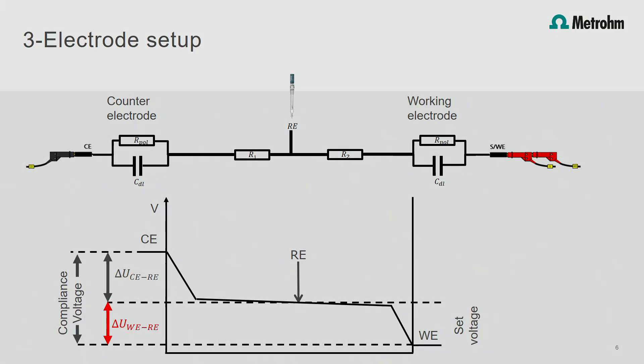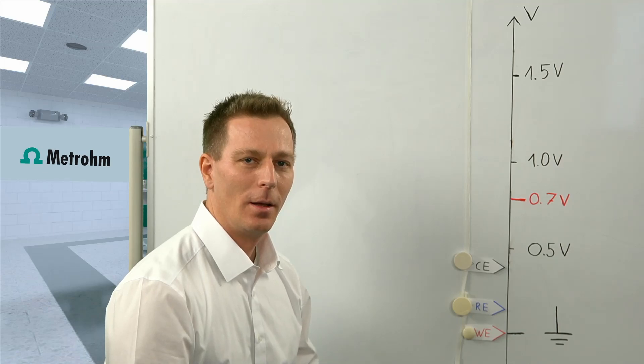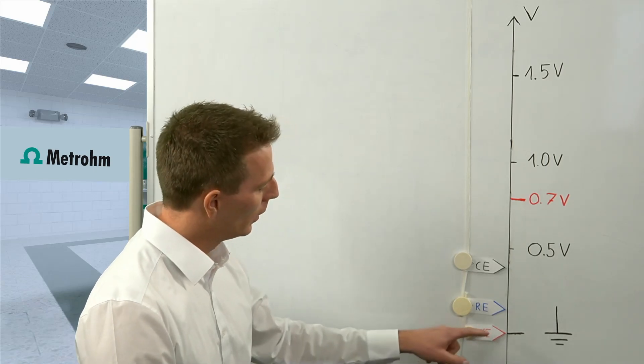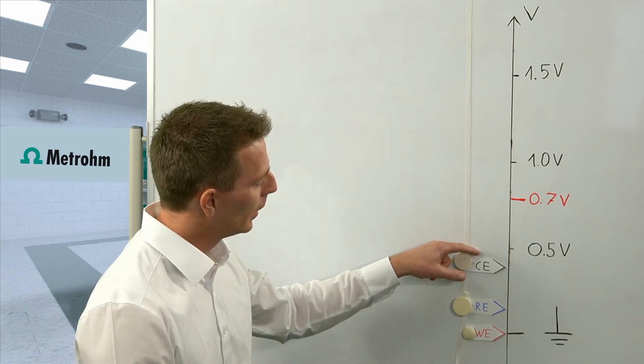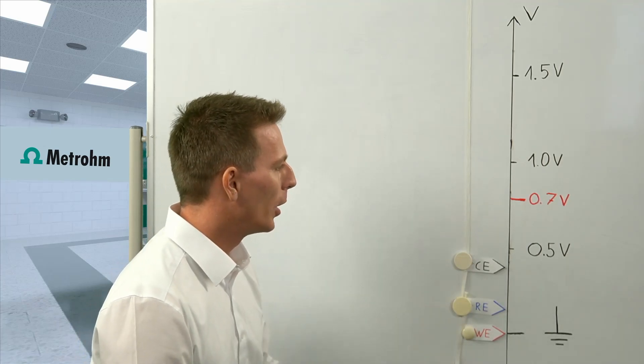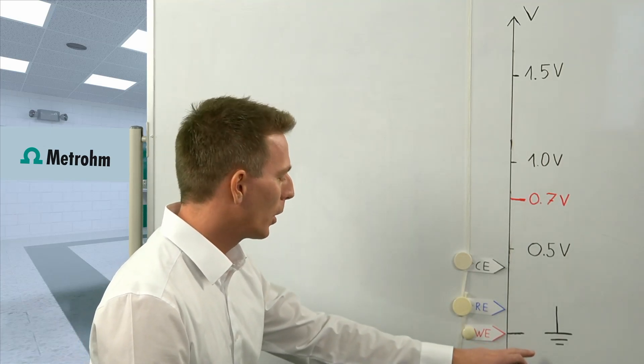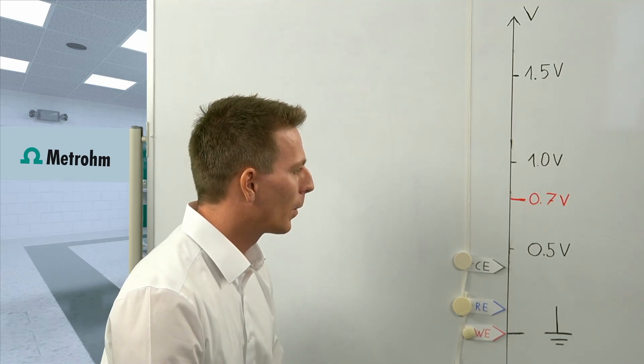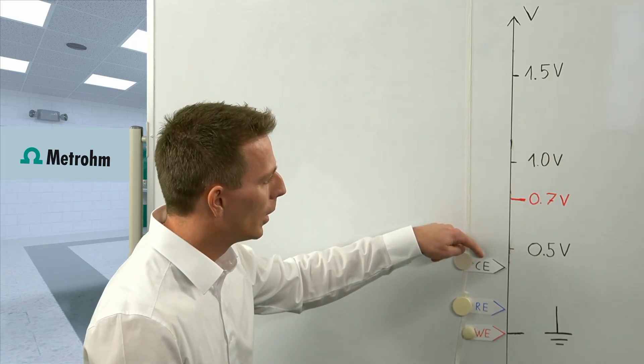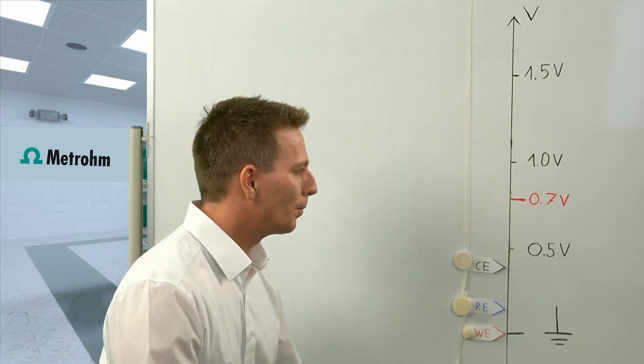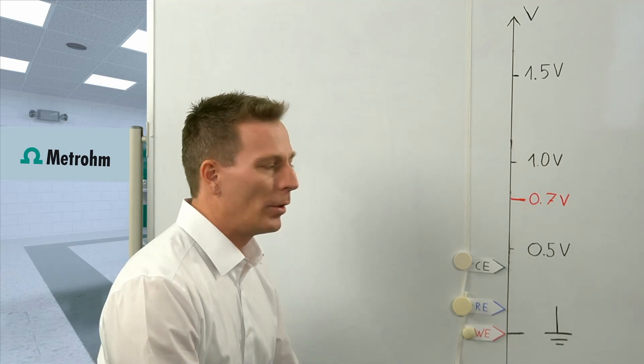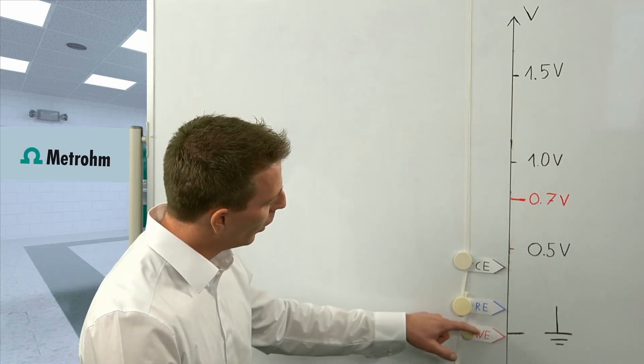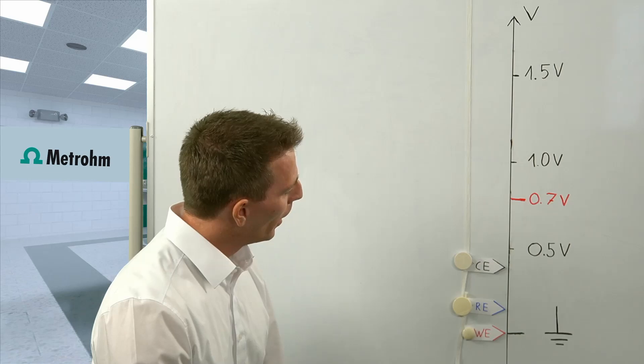Now I will explain the working principle of a potentiostat and how a defined set potential is applied to the working electrode. The voltage is displayed on the y-axis and each label represents an electrode: the working electrode, the reference electrode, and the counter electrode. The most common operation principle of a potentiostat keeps the working electrode on ground — on earth potential — and the active element of the potentiostat is the counter electrode. Before applying a voltage actively, there are reactions taking place at the electrodes and therefore the so-called open circuit potential between working and reference electrode, and reference and counter electrode, builds up.